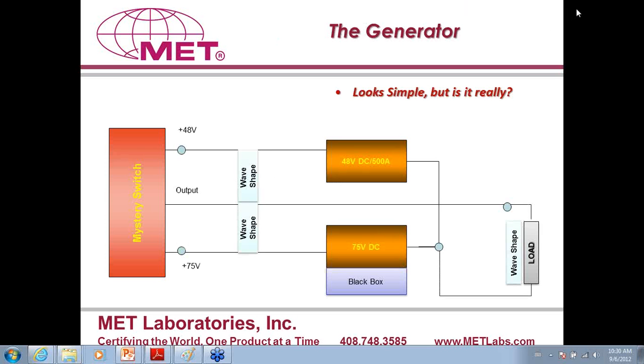Now, how does this generator work? How come the generator we came up with is more unique and more accurate, in my opinion, compared to the generators being used in the industry today? Our generator is based on, I will start from left to right. The red box, which is labeled as mystery switch, is a very high-speed 400 amp switch, which acts as a single pole double throw. It's an electronic switch, not a mechanical switch. It's extremely difficult to find mechanical switches which could operate at these fast rates.